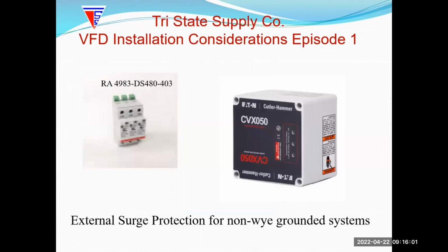If you do have an ungrounded or a resistive ground of any type system, to meet UL it is recommended to add external surge protection to your panel. And this is because, as we're going to see in the next episode, depending on your transformer design that you're supplying to the facility for the drive, you're going to be eliminating that MOV in the drive. So external protection is required for UL.